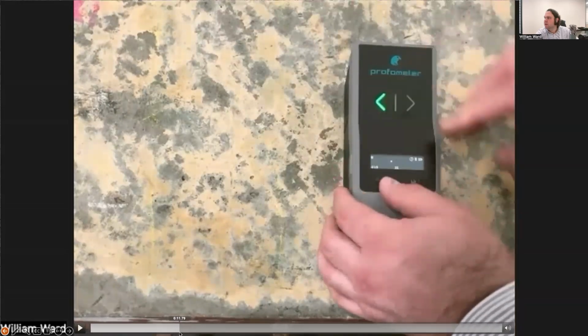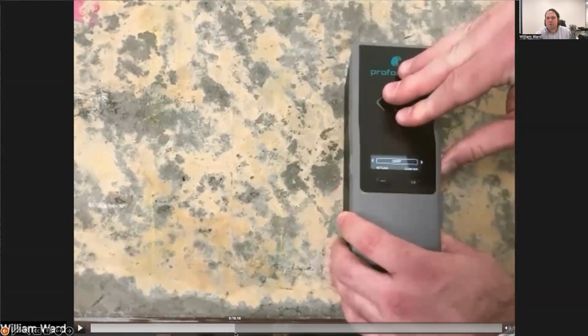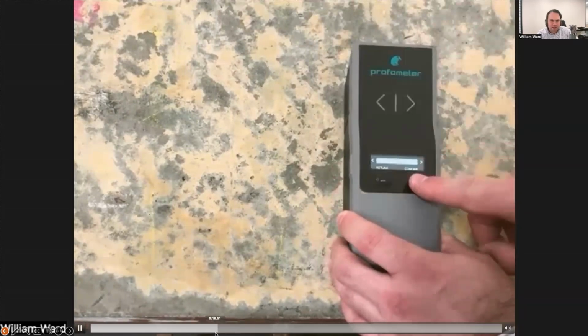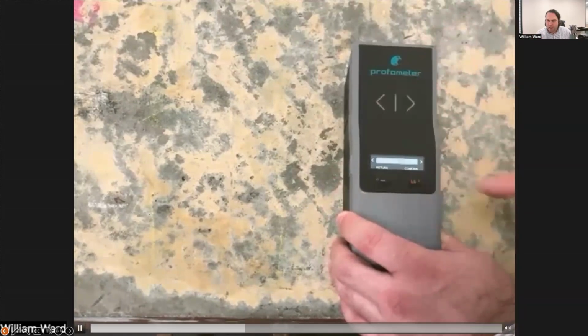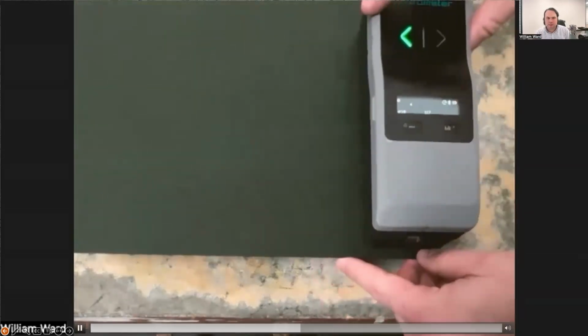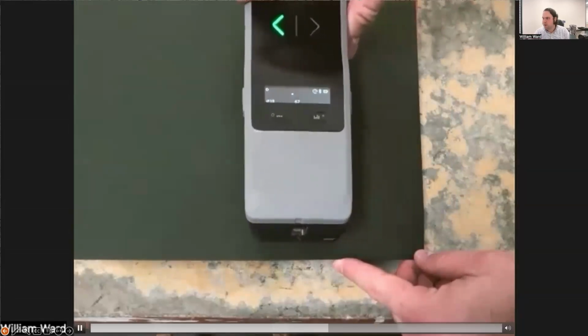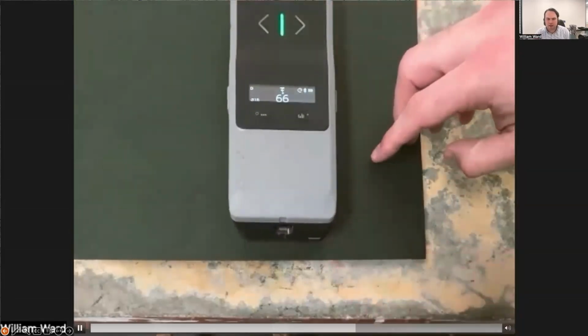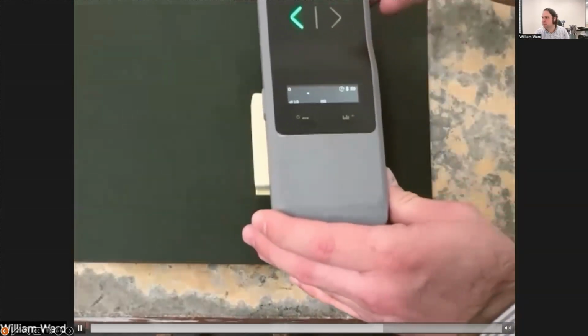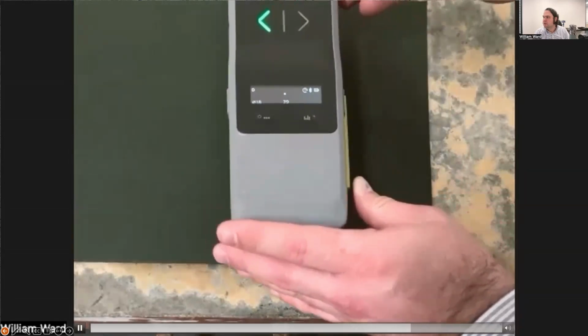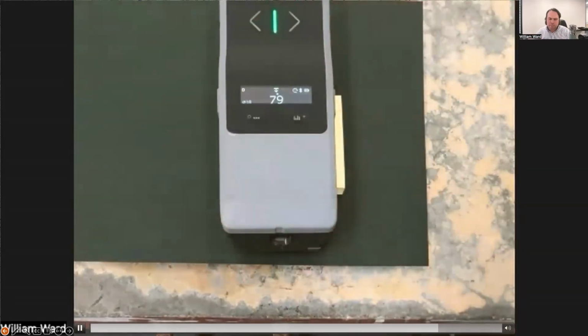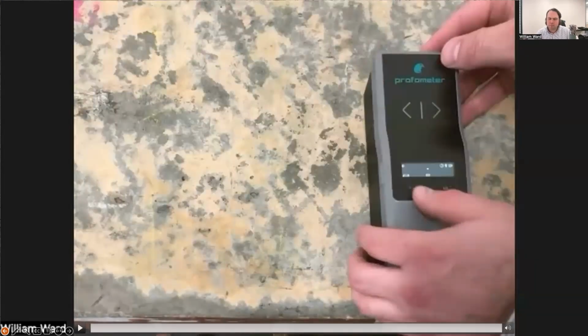This functionality is about the deep measurement range. So we normally operate in a standard measurement range, which ranges down to 80 millimeters maximum. If we wish to use the full 180 millimeter range of the device, and I've just put a block on top of my test block here to make everything deeper, I'm now measuring at 66, and if I go a little bit higher than that, I'll end up measuring up above the 80 mark. So this is the deep measurement mode you'll use to measure cover above 80 millimeters. You don't want to use this unless you have to, as you can no longer estimate bar diameter below around a 50 millimeter depth. And the additional electromagnetic field makes this measurement mode more prone to interference.